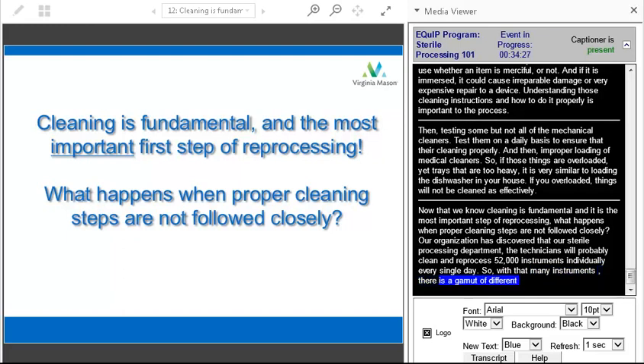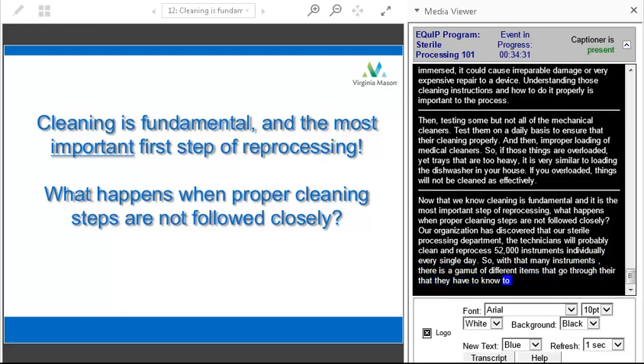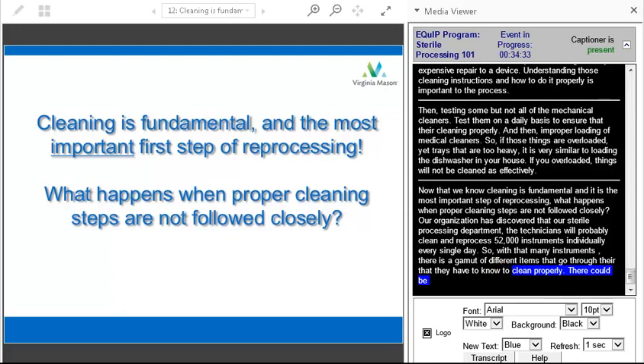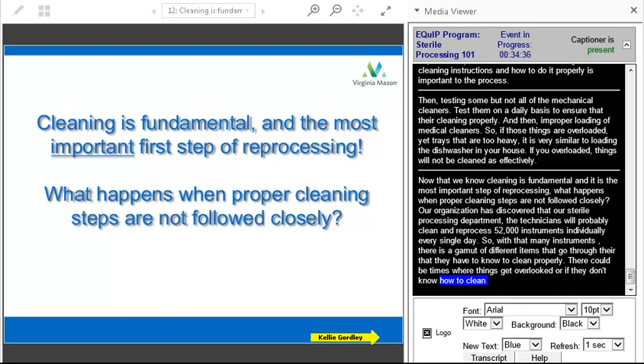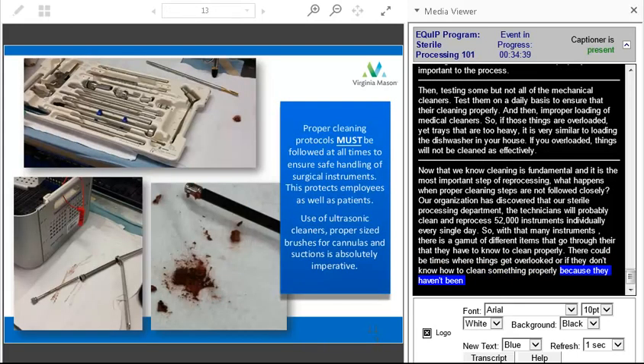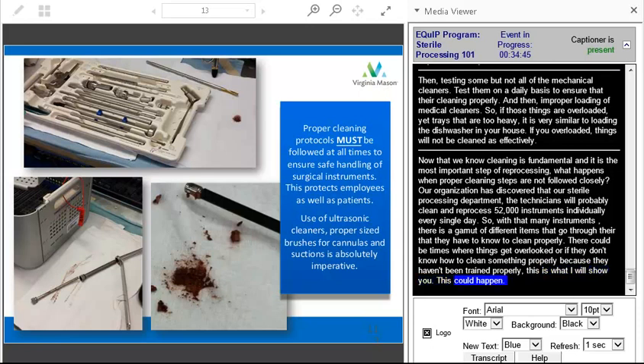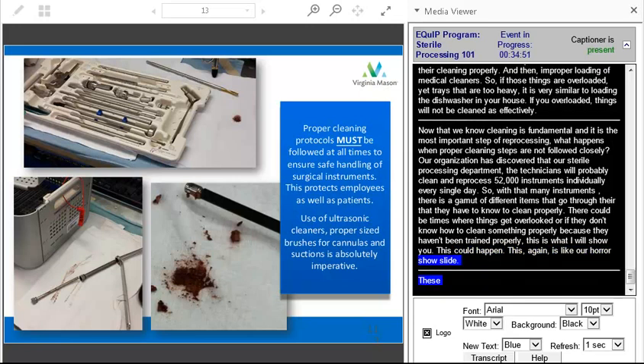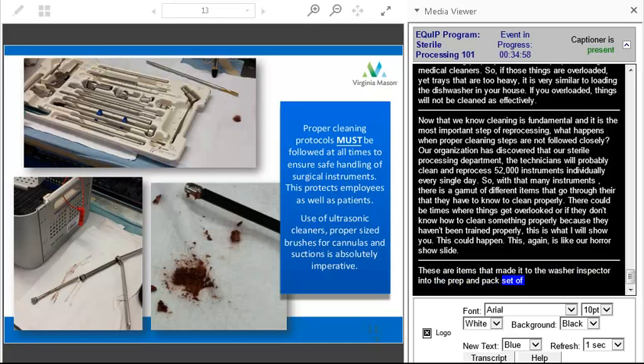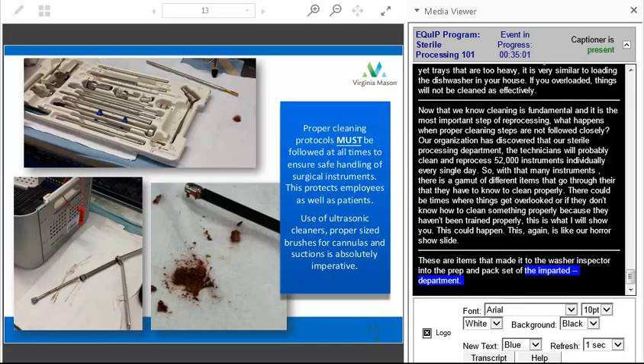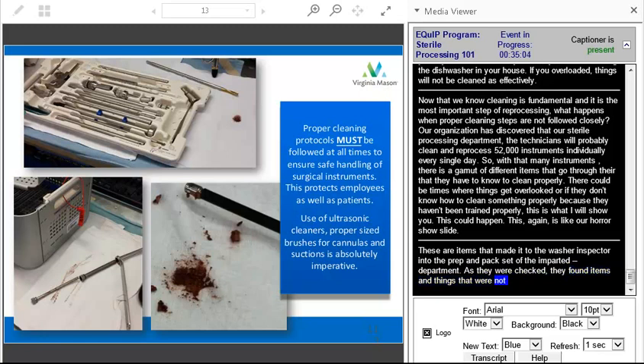There could be some times where things could get overlooked, or if they don't know how to clean something properly because they haven't been trained properly. This is what I will show you. This could happen. So this, again, is kind of like our horror show slide is what I'm calling this. These are items that have made it through the washer disinfector onto the prep and pack side of the department, and as technicians have been assembling and checking for functionality and cleanliness, they have found items and things that were not so clean in their trays. And so their inspection tables have to be broken down, cleaned. These devices have to be sent back to the decontamination area for recleaning.